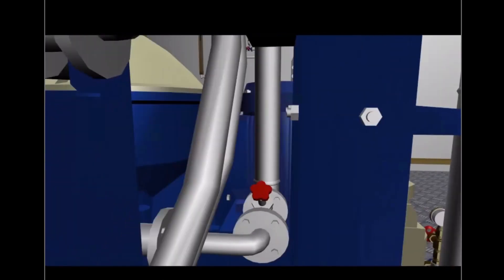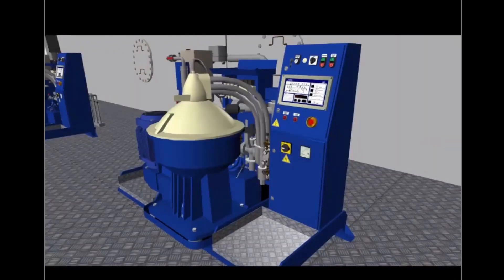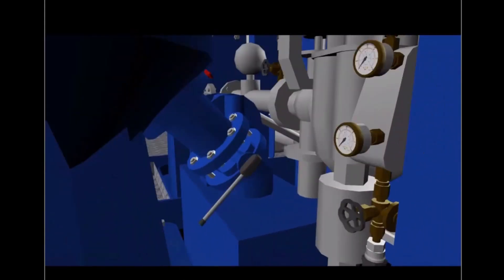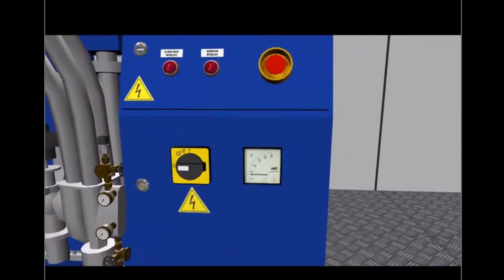The flow regulating valve should initially be set to about 50% open. Open the sludge outlet valve. Now switch on the power supply.